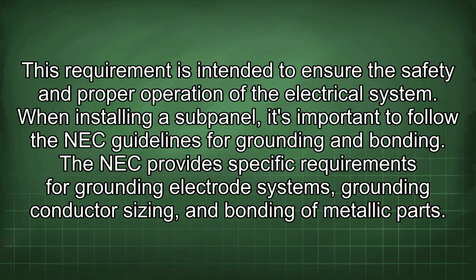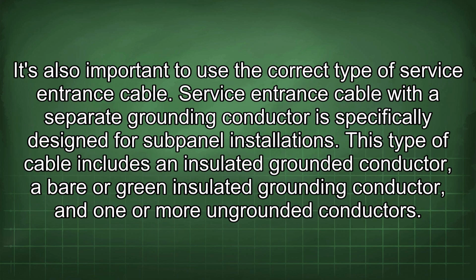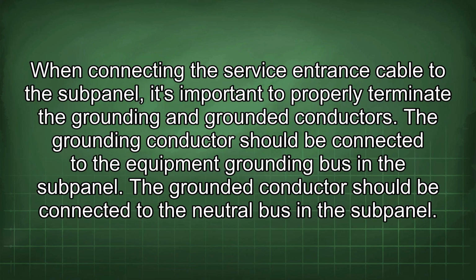When installing a subpanel, it's important to follow the NEC guidelines for grounding and bonding. The NEC provides specific requirements for grounding electrode systems, grounding conductor sizing, and bonding of metallic parts. It's also important to use the correct type of service entrance cable. Service entrance cable with a separate grounding conductor is specifically designed for subpanel installations. This type of cable includes an insulated grounded conductor, a bare or green insulated grounding conductor, and one or more ungrounded conductors.